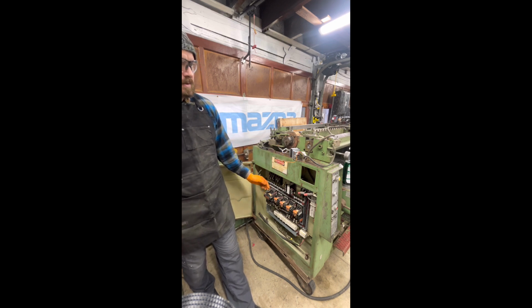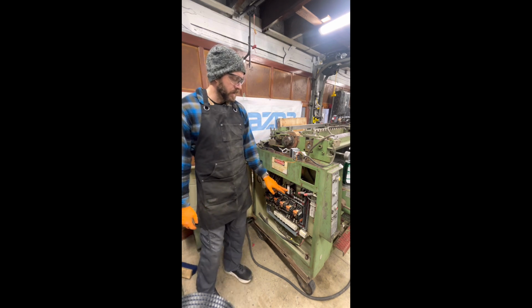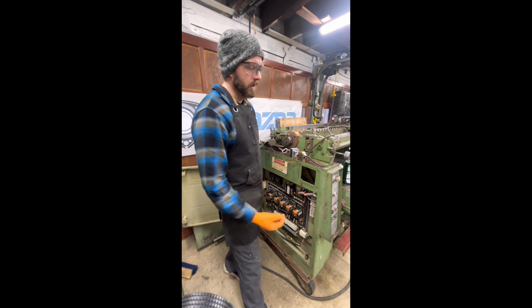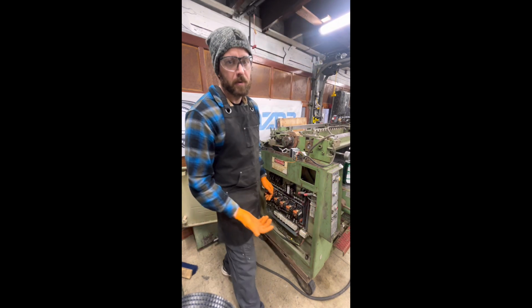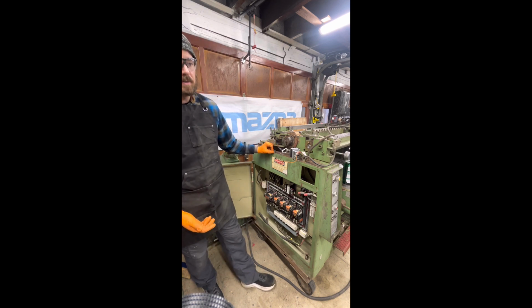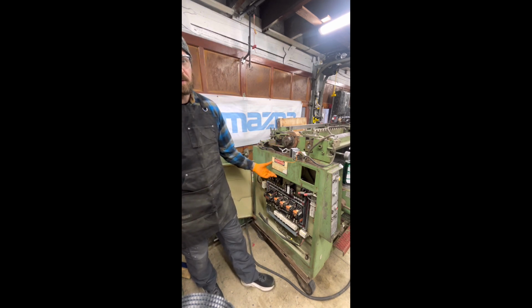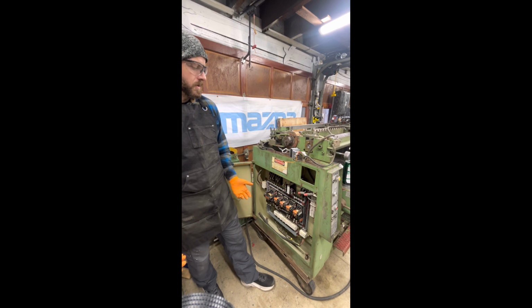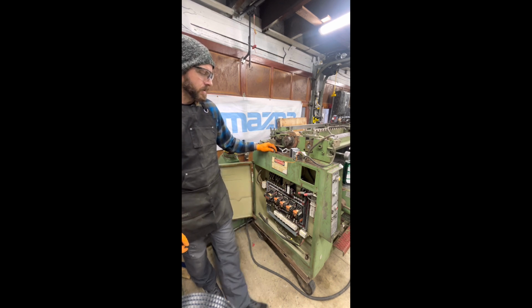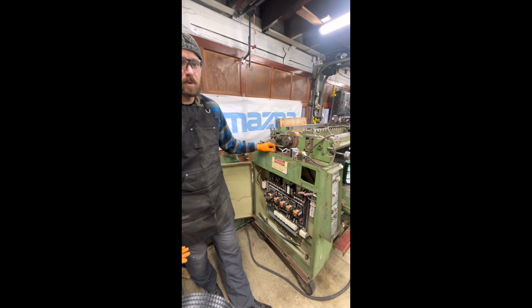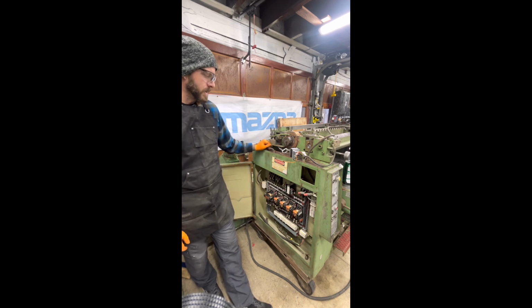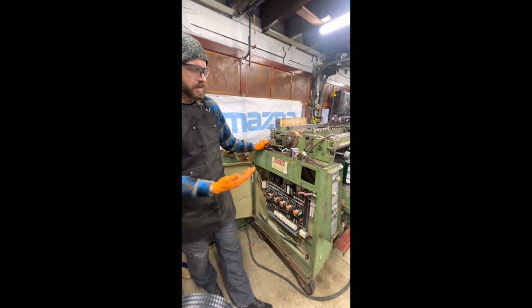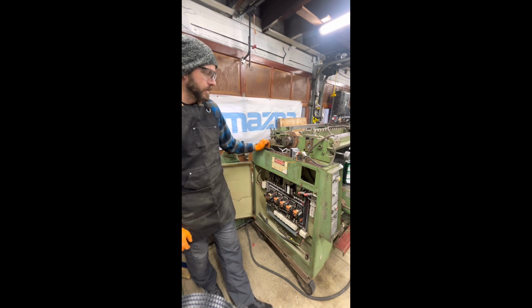However, it's not using the negative, we'll call it, from the transformer. So if something goes wrong with the start and stop button up front, you're not going to get a shock because the transformer is going to be grounded to the chassis. So you won't end up earthing yourself to the ground and getting a 120 volt shock. Typically on a lot of newer machines, like I said, we would use 24 volt for that type of stuff just because it's a little lower voltage, less danger involved there. However, these isolation transformers do make it safe for utilizing start-stop buttons with higher voltage equipment.